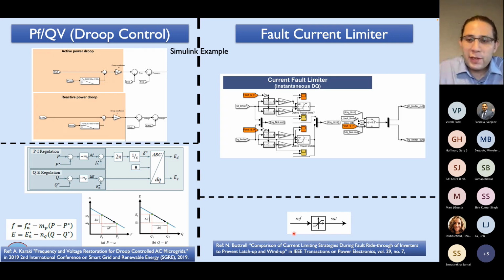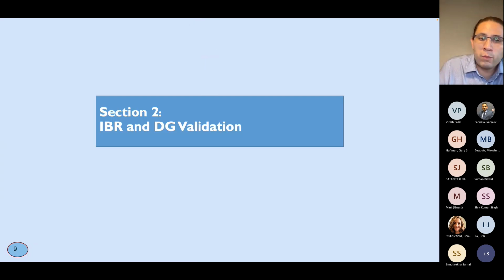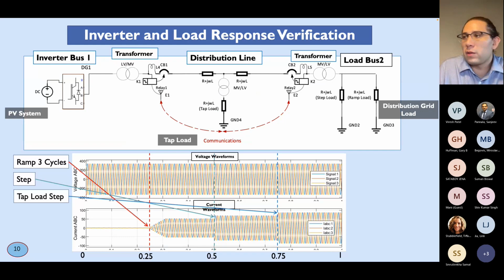So the control basically designs for short circuit fault studies, and we consider the limit that we have a certain value that prevents the signal from passing beyond a threshold value, which is exemplified in this small block by a saturation factor. The common one we utilize is 1.2 for inverters for construction based on manufacturer documentation. I will talk about the inverter resource and the validation of our construction.